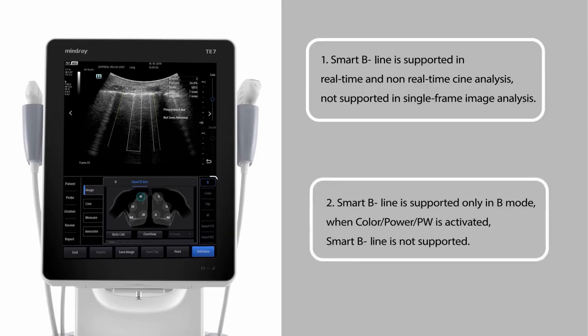Smart B-line is supported only in B-mode. When color, power, or pulsed wave is activated, Smart B-line is not supported.